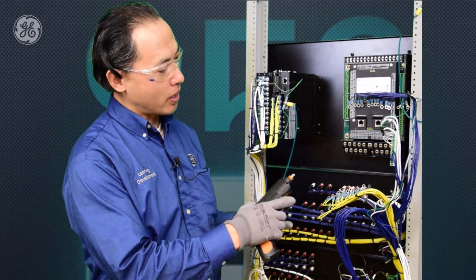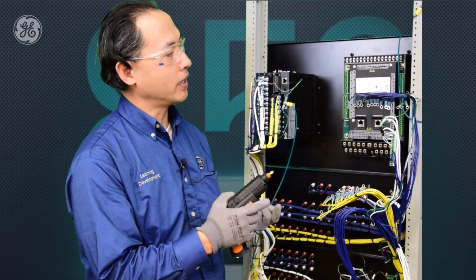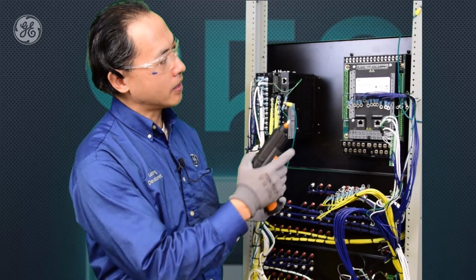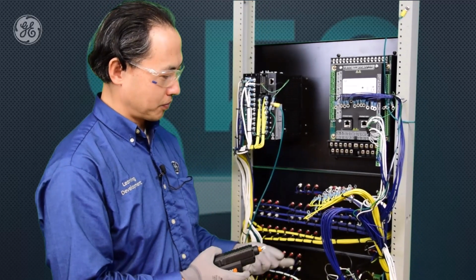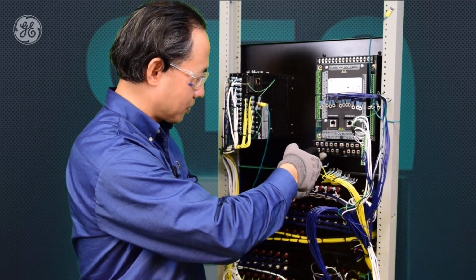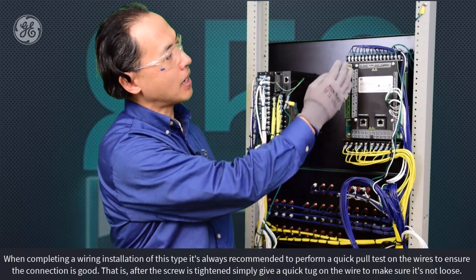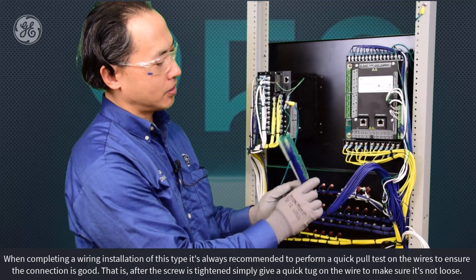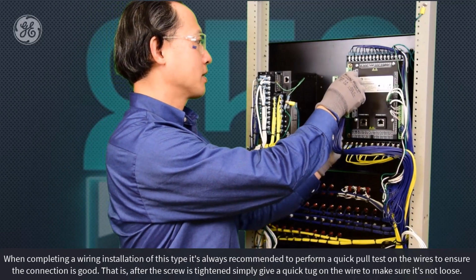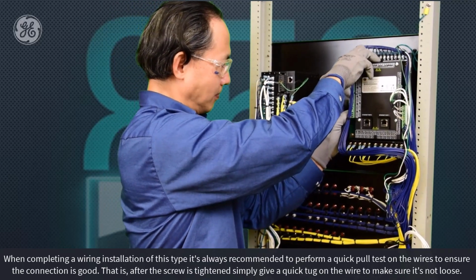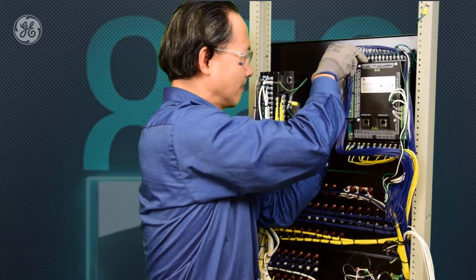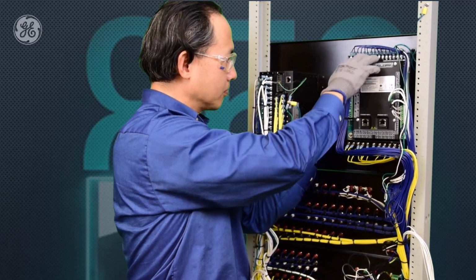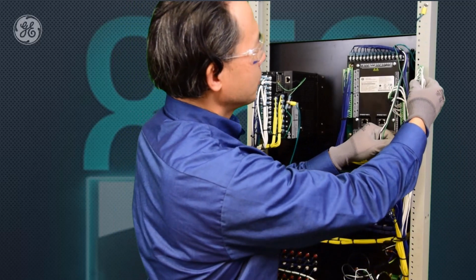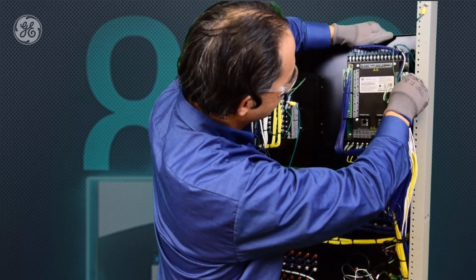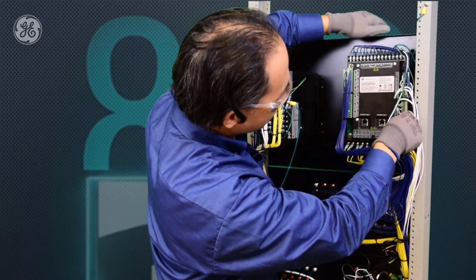First I'm going to wire the bottom CT-VT inputs, then the top output relays and the control power, then plug into the RTD terminals and the digital inputs, communication port, and analog outputs. So first I'm going to put in this. Okay, now I finished the rewiring of the CT-VT at the bottom and the output relay and the control power on the top. I'm going to plug in the terminal blocks. First, I'm going to plug in the RTD terminal blocks. And then the digital inputs, the communications and analog outputs.